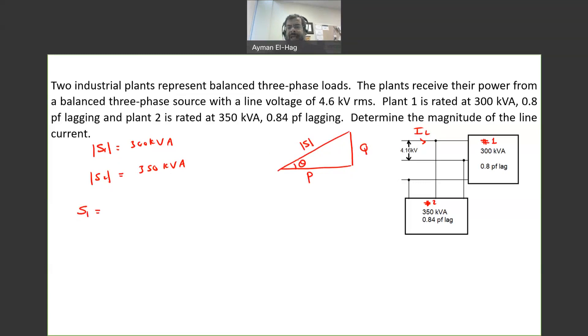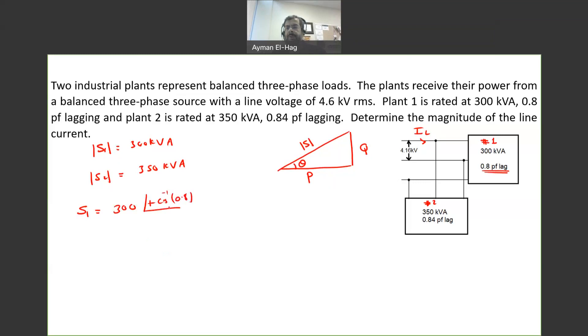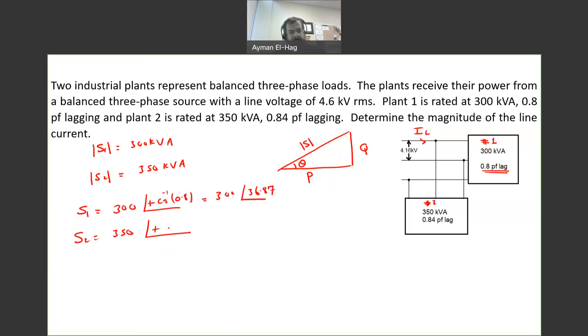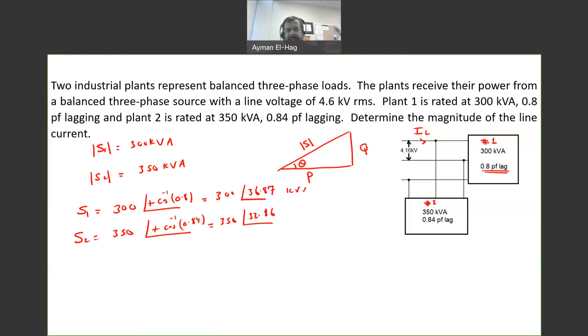So we need to find S1 and S2 as vectors. This is straightforward because the angle is the same as the power factor angle. Since we know the power factor and that it is lagging, we can find the angle. S1 is equal to 300 at angle positive cosine-inverse of 0.8, which gives 300 angle 36.87°. S2 is equal to 350 at angle cosine-inverse of 0.84, which gives 350 angle 32.86°. Both in kVA.